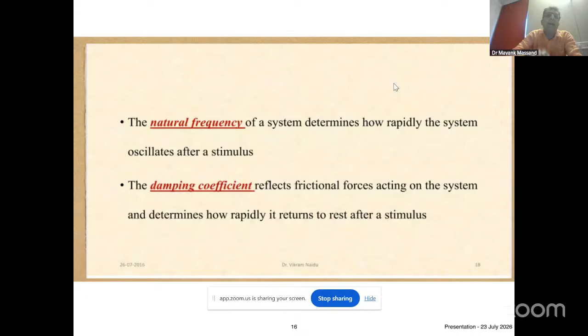Now, when we talk about the natural frequency, it is important for an IBP system to have a high frequency, because if, suppose, the person goes into AF, atrial fibrillation, in spite of that, the arterial blood pressure monitor should have the tendency to reproduce that waveform and interpret what is actually going on. So 8 times is the fundamental frequency of the arterial waveform. Okay, so therefore, for a system to remain accurate, this line is very important.